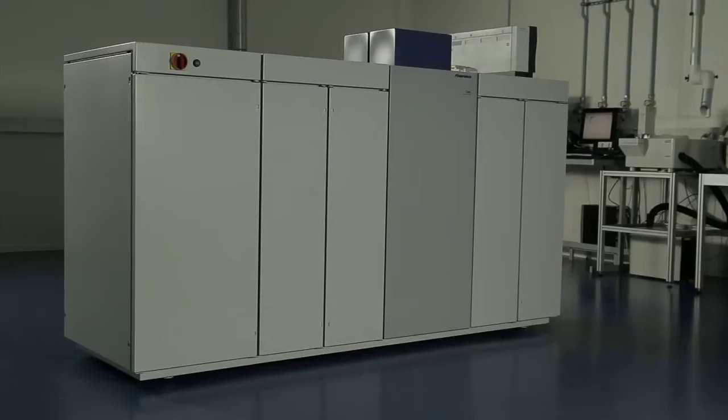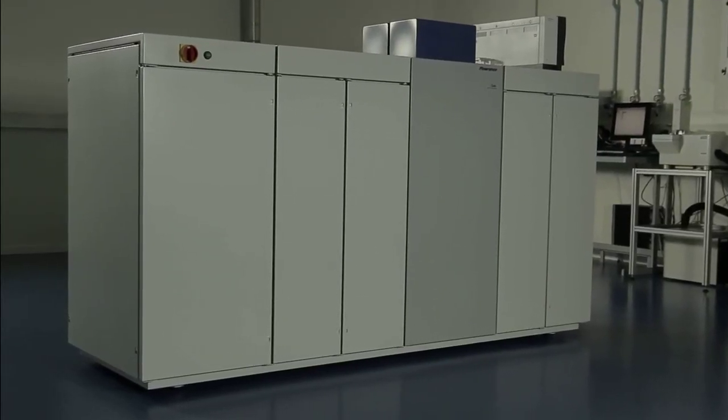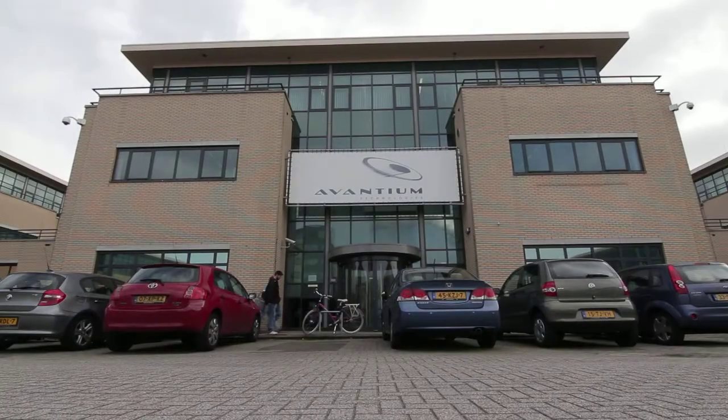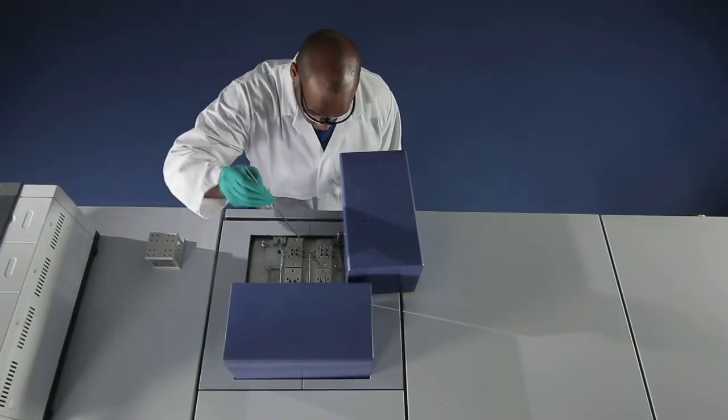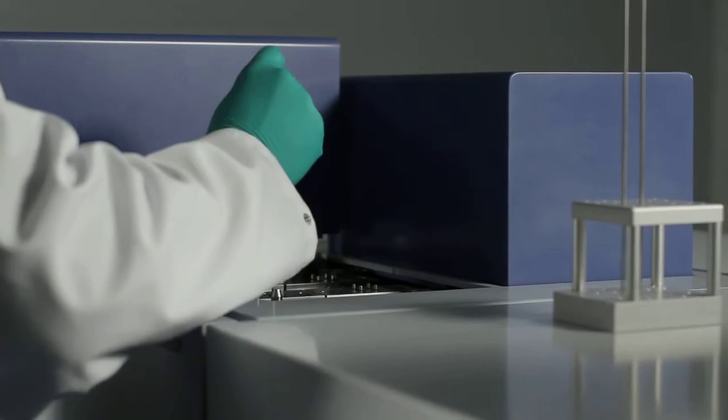The Flowrence has been developed at some of the most advanced catalytic research laboratories in the world. We believe our Flowrence reactor system is unique because we introduced various innovative solutions to test catalyst samples on a small scale. The solutions to control the exact amounts of feed material to the reactors, the pressure control in the reactors, and the way we can collect the samples of the reactors contribute to a system which will allow the testing of catalysts with minimal effort.